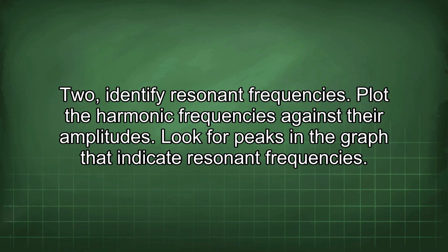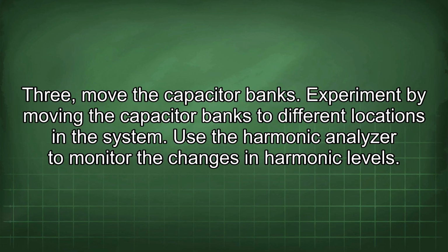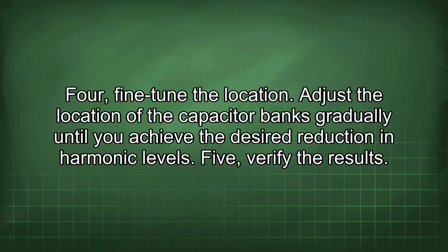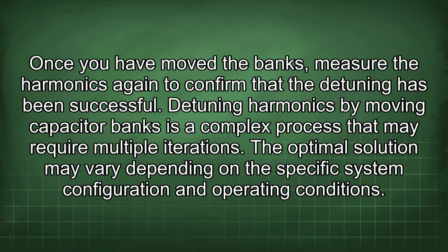Plot the harmonic frequencies against their amplitudes. Look for peaks in the graph that indicate resonant frequencies. 3. Move the capacitor banks. Experiment by moving the capacitor banks to different locations in the system. Use the harmonic analyzer to monitor the changes in harmonic levels. 4. Fine-tune the location. Adjust the location of the capacitor banks gradually until you achieve the desired reduction in harmonic levels. 5. Verify the results. Once you have moved the banks, measure the harmonics again to confirm that the detuning has been successful.